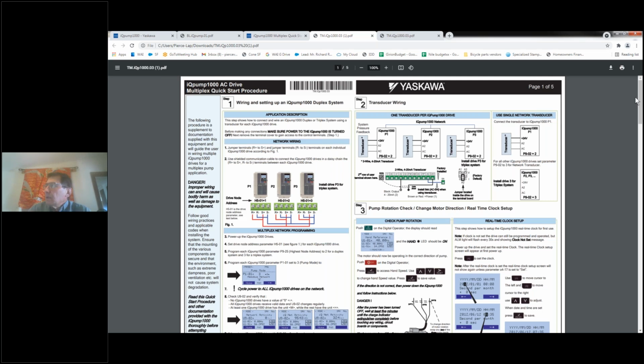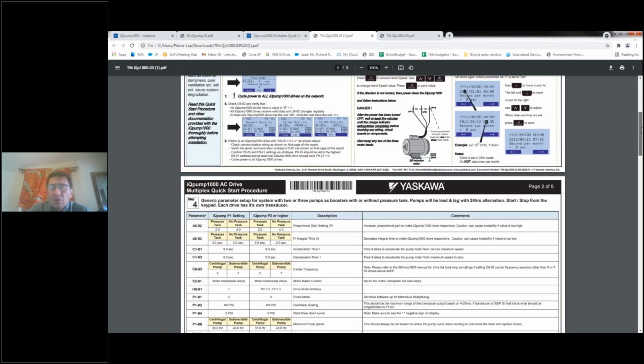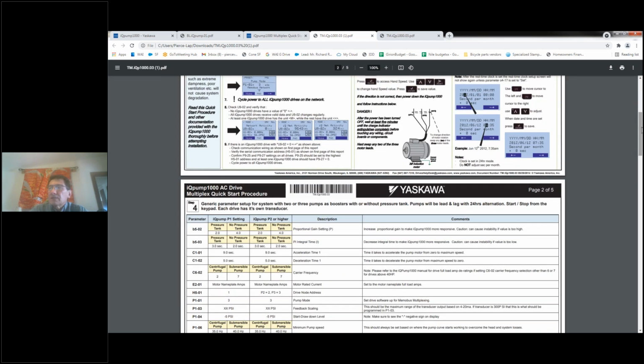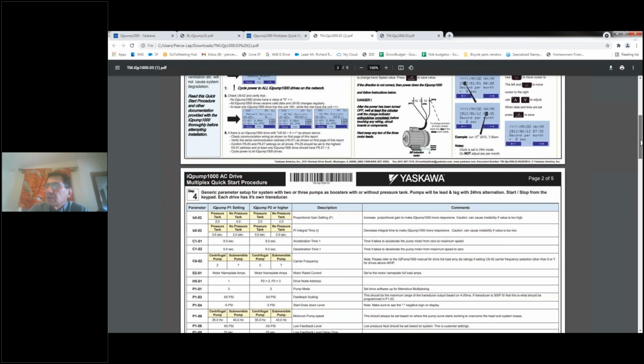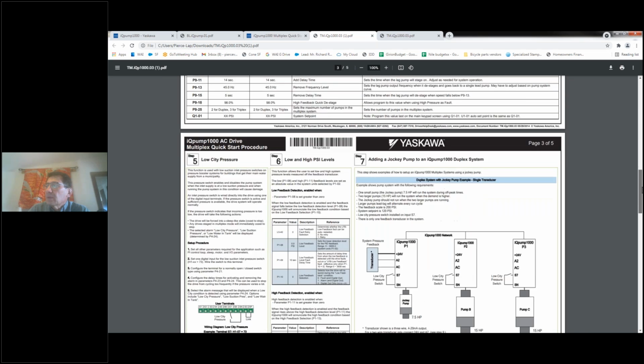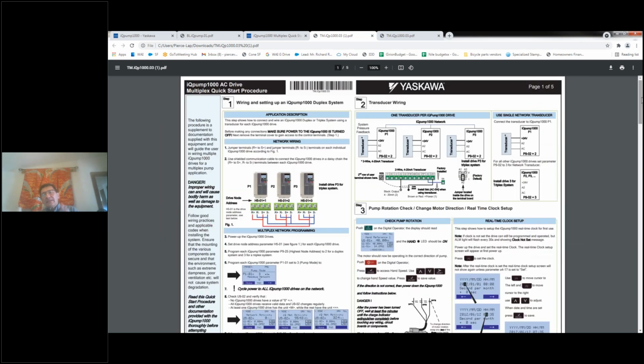So it's not going to cost you a lot of extra money to use the multiplex system from a technical and support standpoint, because the documentation is very good. Now, all the standard IQ features that you are used to will present themselves in the multiplex system as well as in a simplex system. And I will say that is similar to the other brands of multiplex versus simplex systems that I've seen out there on the marketplace. There's no reason to have a feature degradation, because remember, you have a master drive, and that master drive has all the features that you require for the water application.